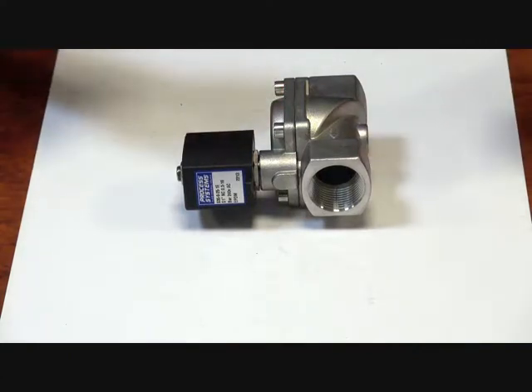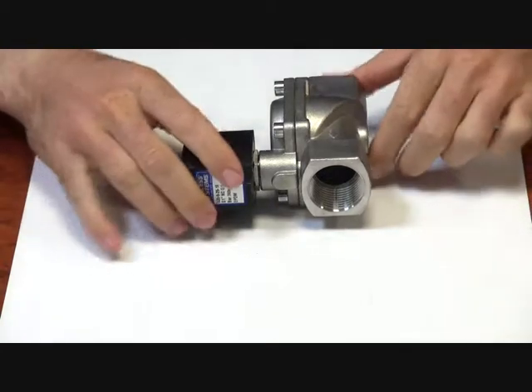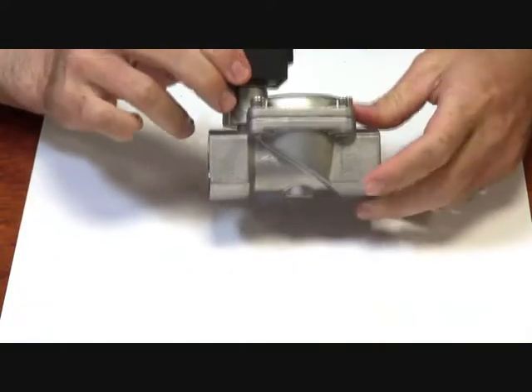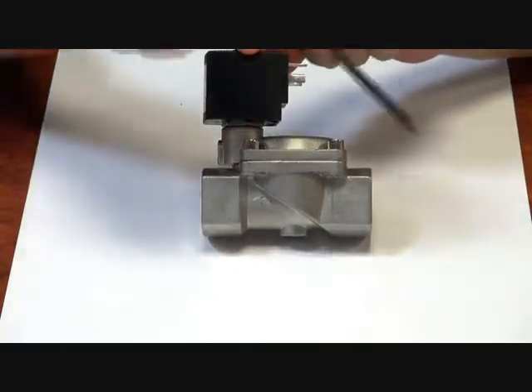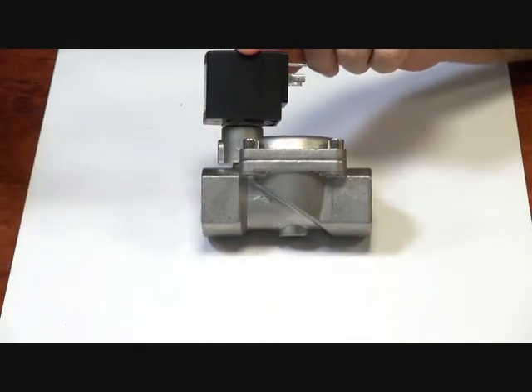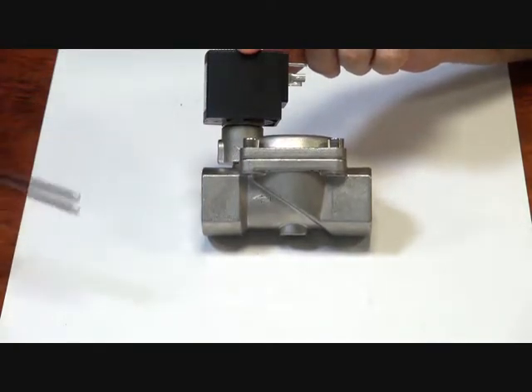So the body here is 304 stainless steel. Now it's a differential valve, so what does that mean? Well, if you see this little arrow of flow on the side here, it means there has to be a difference in pressure between the inlet and the outlet of the valve. So this particular model, which is a 1 inch, has a 0.3 bar differential.